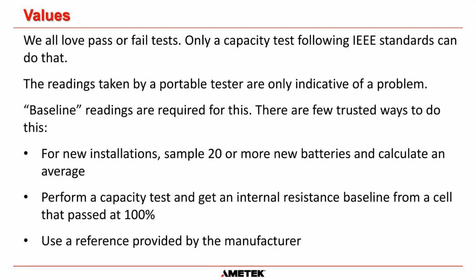The third way to do it is to use a reference provided by the manufacturer. Now, that's not the best way to do it because you don't know what tester the battery manufacturer is using. You don't know how they are getting that information. There are always going to be discrepancies between different manufacturers of testers, and even between two devices from the same manufacturer. So it's much better to use the actual device that you are going to be using to create that baseline. I hope that makes sense. It's extremely important to get that baseline, because the readings mean nothing if you don't have something to compare them to.